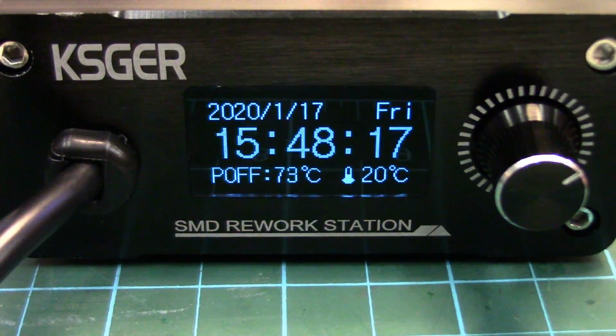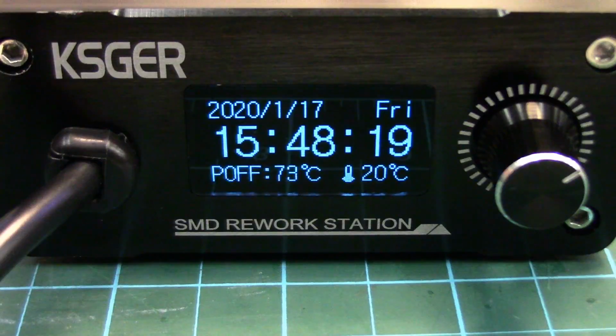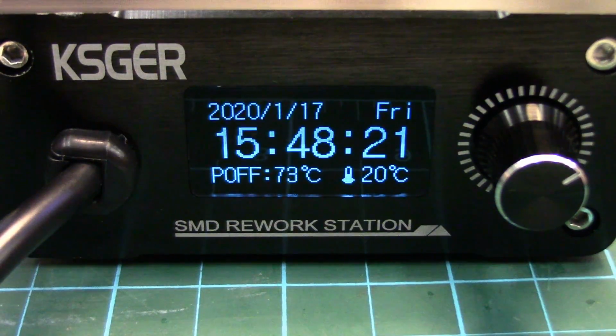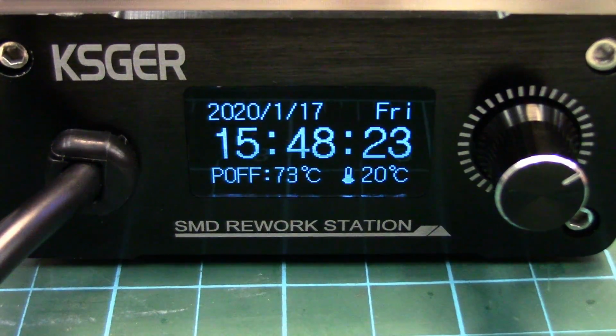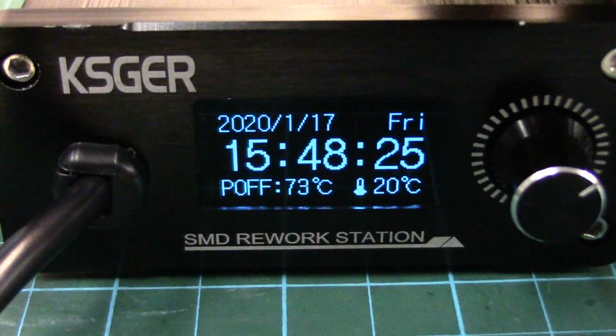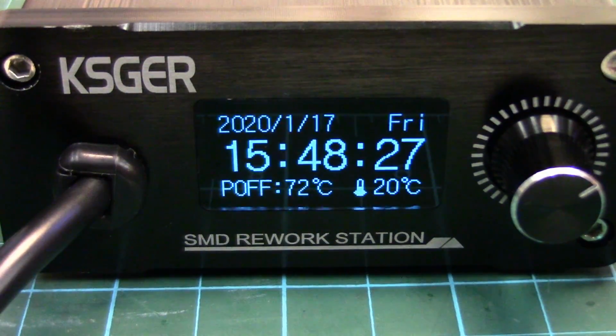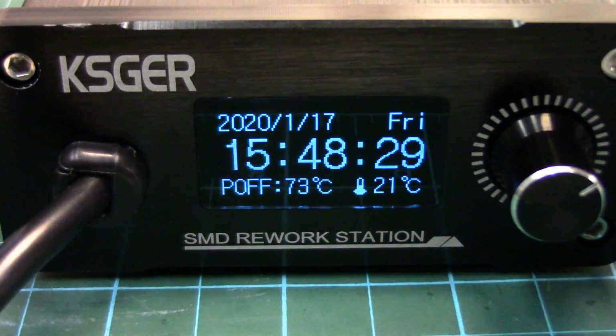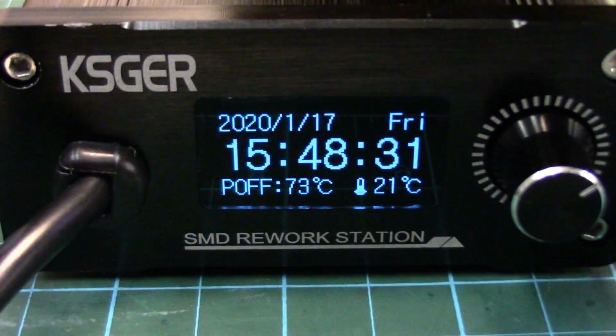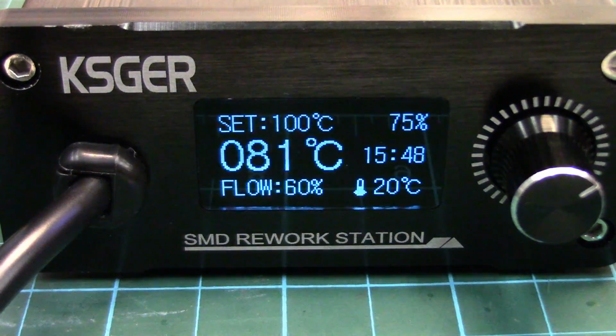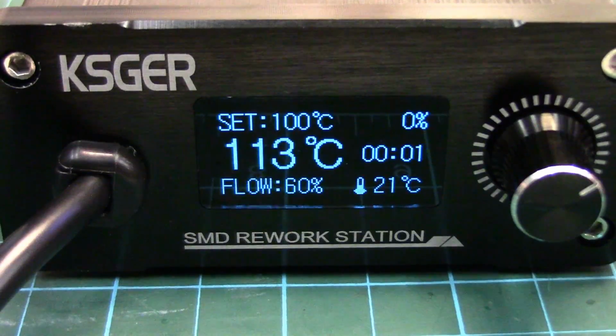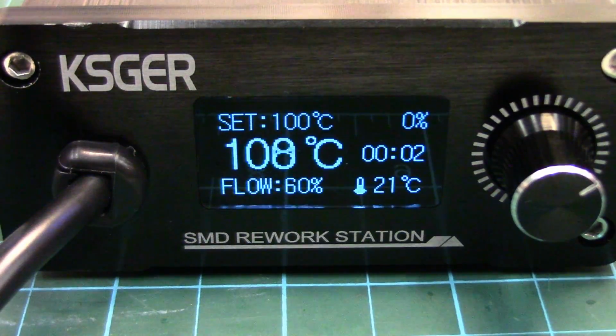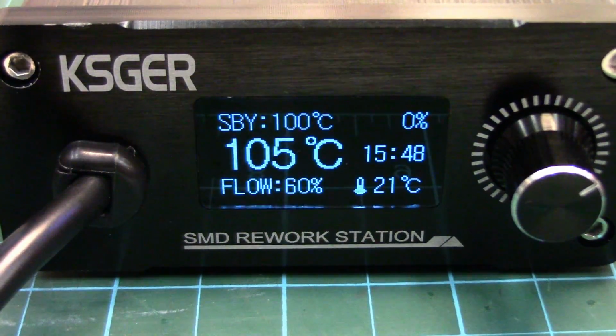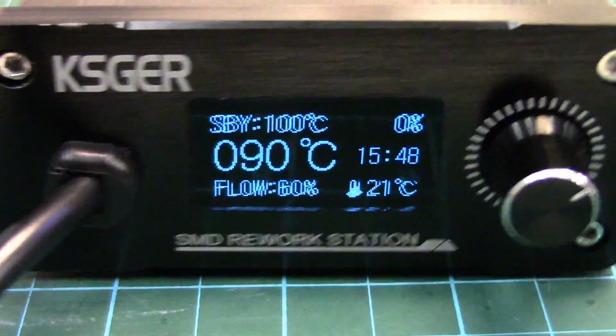So I've got the wand out of the cradle because this will show a couple of different things depending on if it's in the cradle or out of the cradle, and if you've got that little power push button on the back turned on or off. So with the button turned off, it shows power off. If we turn it on, it's operating. And if we put the wand in the magnetic cradle, instead of power off, it shows standby.